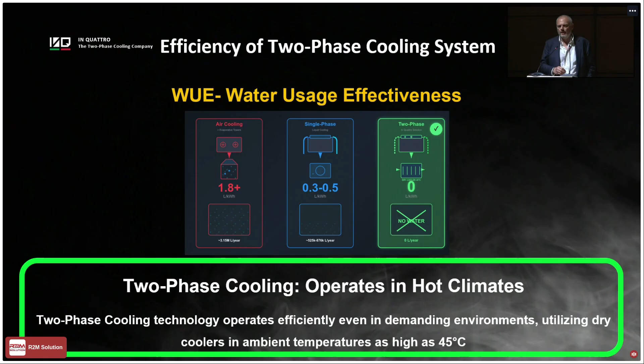And today we are also working on developing a new patent in order to increase this limit up to 60 Celsius degrees. Why? Because even when the external ambient temperature is 35 Celsius degrees, on the surface of the heat exchangers on the roof of the data center or outside the data center during the summer season, you can reach higher temperatures, like 50 or 55 Celsius degrees. So this is the reason why we are going to improve this value. But not only for this, but also for a European project where we are involved with other partners, and this project will be presented later.